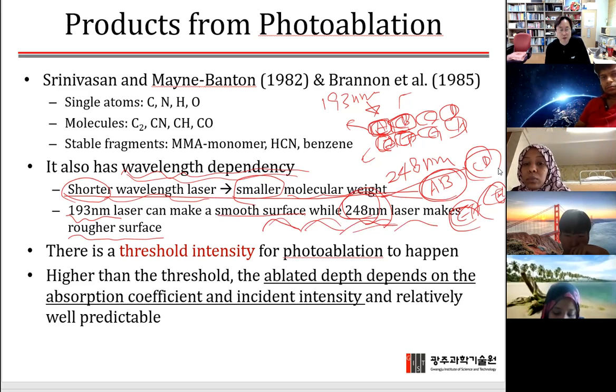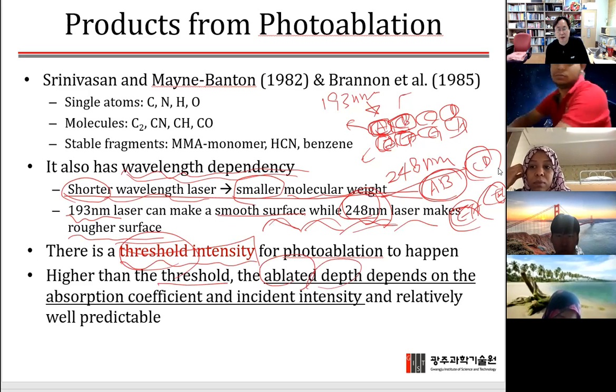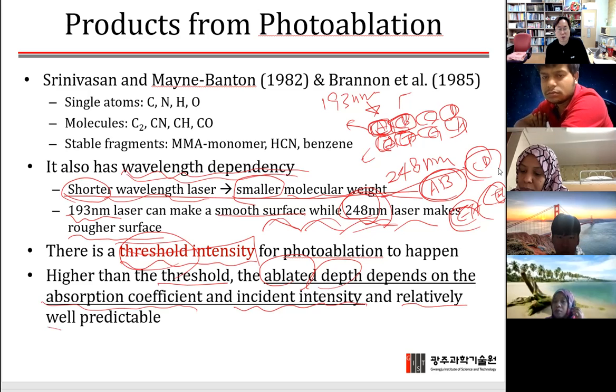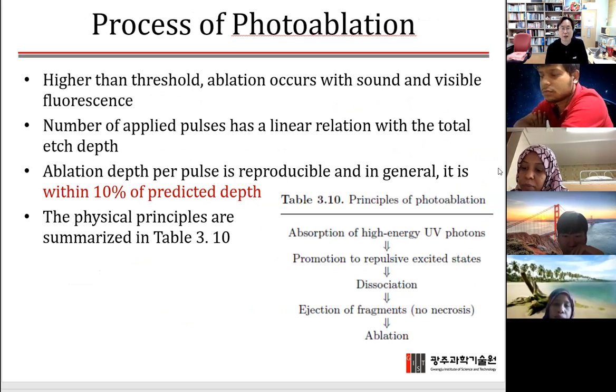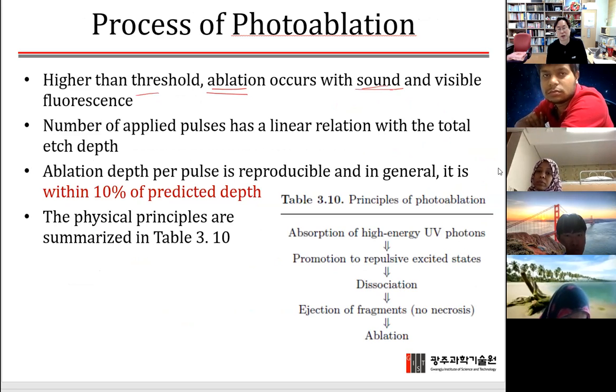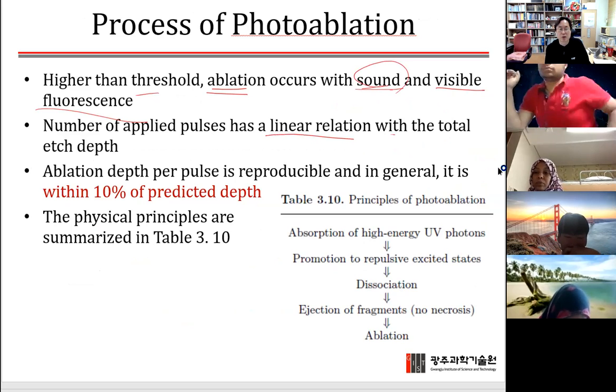And also for photoablation, there is a threshold intensity. So you need to have intensity higher than some specific threshold, otherwise this will not happen. Above the threshold, the ablative depth depends on the absorption coefficient of the tissue and also the intensity of the incident laser, and these are relatively well predictable. So above the threshold, ablation will happen, and when the ablation happens, it makes a sound like that, and visible fluorescence, like a bluish color. The number of applied pulses has a linear relation with the total etch depth.